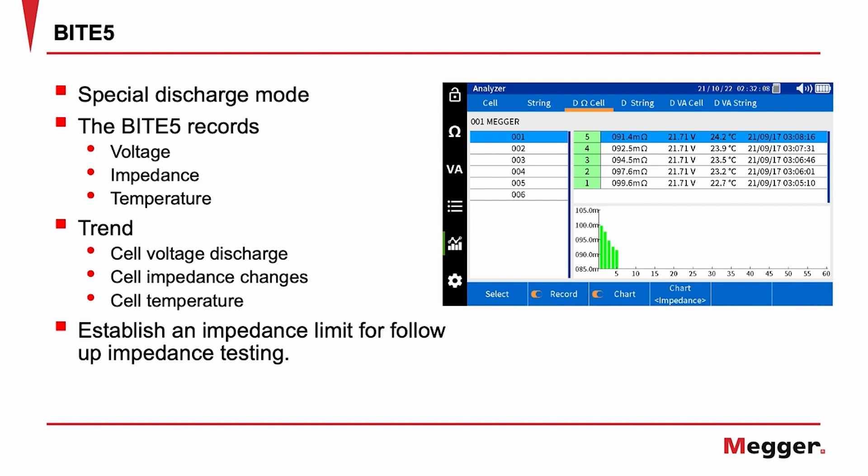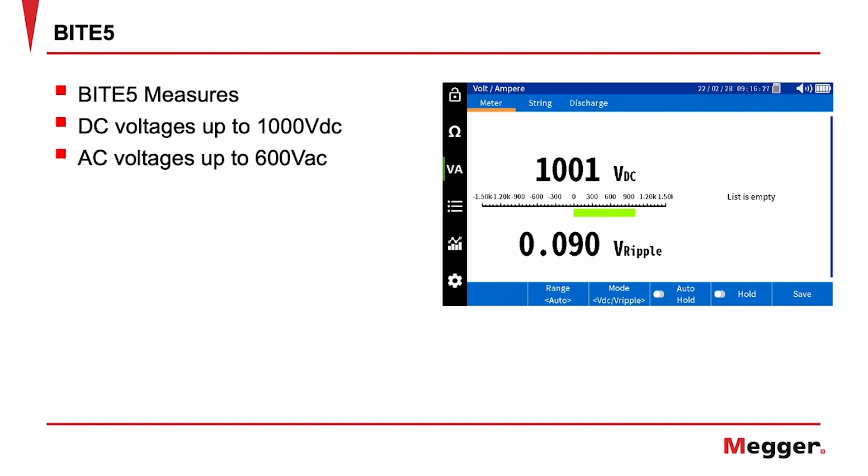The impedance value recorded during the discharge test can then help establish an impedance limit for follow-up impedance testing. The BITE 5 can also measure and record DC voltages up to 1000 volts DC and AC voltages up to 600 volts AC.